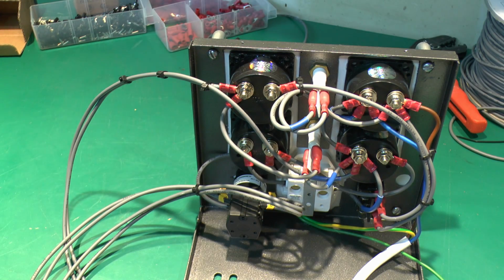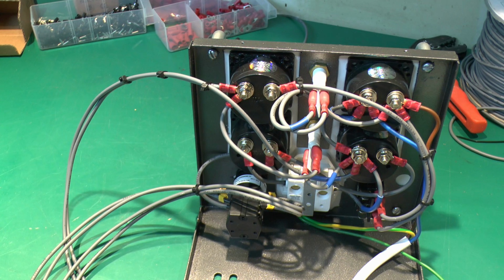So the switch will turn on and off basically the transformer and the output, but single pole only, and it's really there just as a convenience item. It's not intended for isolation purposes, because if you want to isolate the thing on the output, just unplug it - that's far safer than relying on any kind of switch.